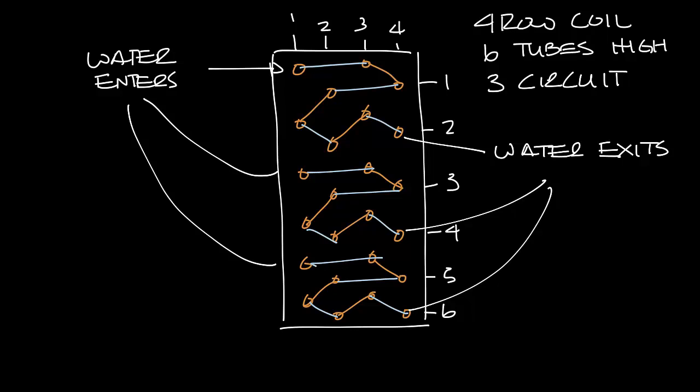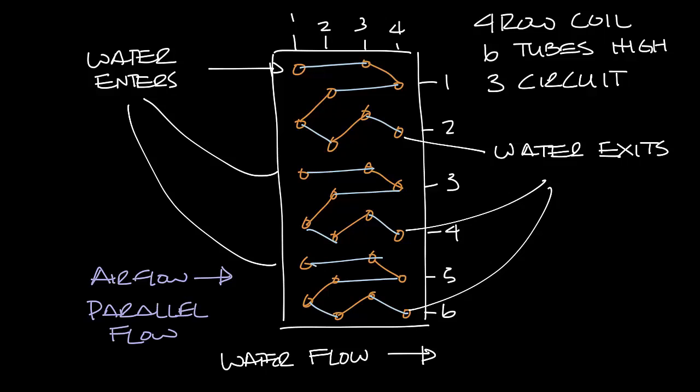So the way I drew this water coil, the water will flow from left to right. If you remember back to the counter flow and parallel flow podcast, if the air flow is moving in the same direction left to right, this is a parallel flow water coil. And if the air is moving in the opposite direction from right to left in the drawing, then this is a counter flow water coil.